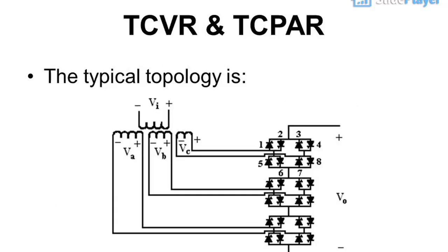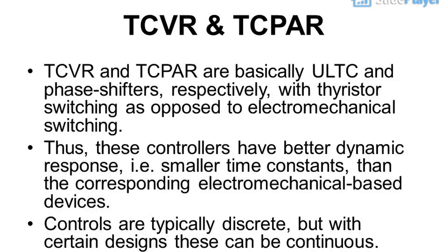TCVR and TCPAR: TCVR and TCPAR are basically ULTC and phase shifters, respectively, with thyristor switching as opposed to electromechanical switching. Thus, these controllers have better dynamic response, i.e., smaller time constants, than the corresponding electromechanical-based devices. Controls are typically discrete, but with certain designs these can be continuous.